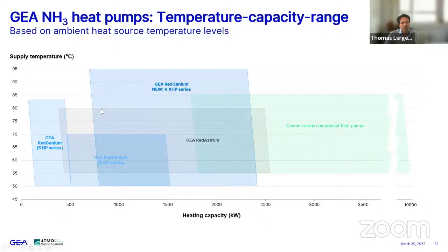And on a smaller capacity range, if you take the smallest models or the smallest type size of this heat pump series or the compressor series that's implemented, you can switch off the cylinders, and with the same efficiency you can still go to part load capacities. So yeah, your capacity range even widens to smaller capacities. So this is a very neat temperature application range that we can serve with our ammonia standard heat pumps.